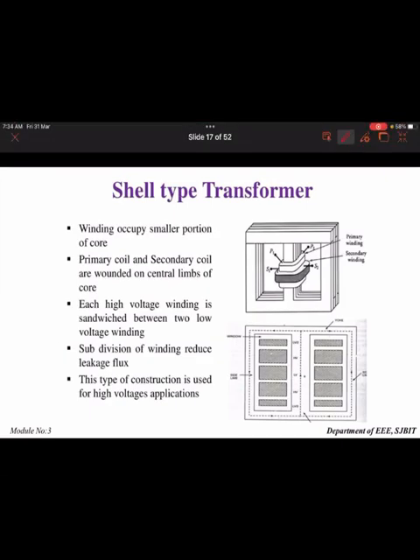In the shell type, you can observe the core forms two hollow windows, and the windings are placed in between. Both the primary and secondary windings are placed on the same limbs. The winding occupies a very small portion, and each high-voltage winding is sandwiched between two low-voltage windings — so both LV and HV windings are placed together. This type of construction is used for high-voltage applications.